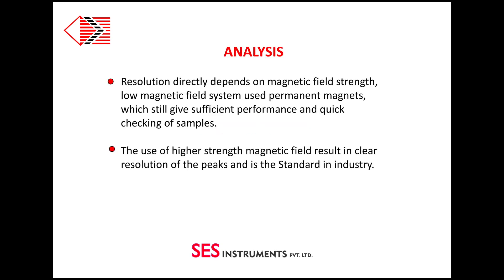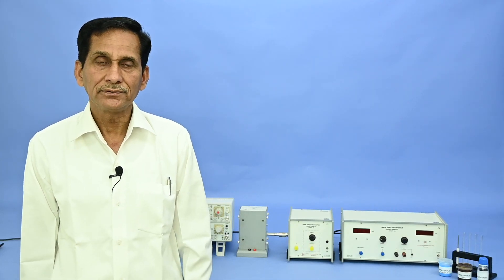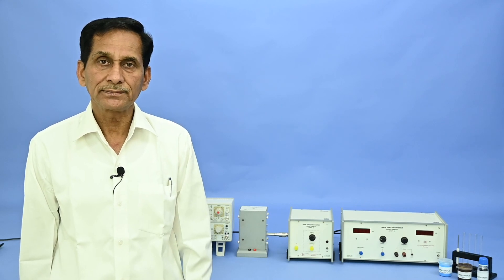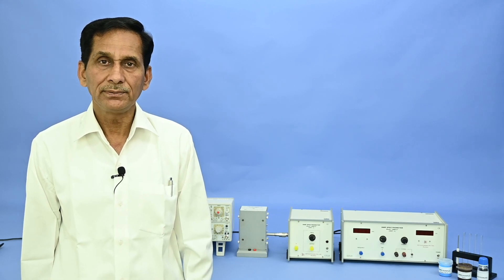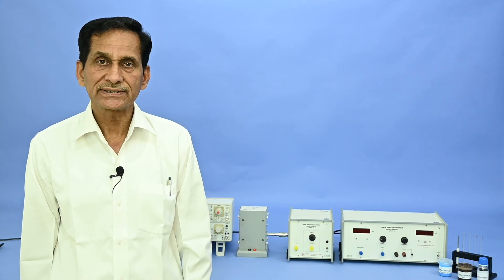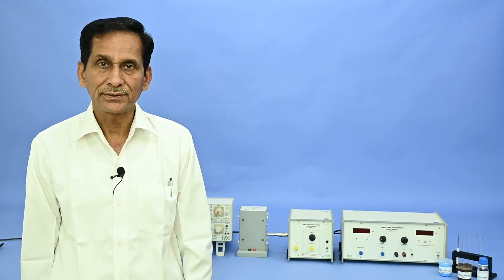Resolution directly depends on magnetic field strength. Low magnetic field systems use permanent magnets which still give sufficient performance and quick checking of samples. The use of higher strength magnetic fields results in clearer resolution of peaks and is standard in industry. Thank you for watching this video. For details of our other products, please visit our website www.sesinstruments.com. Have a nice day.